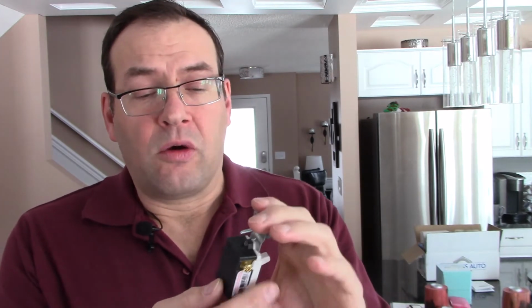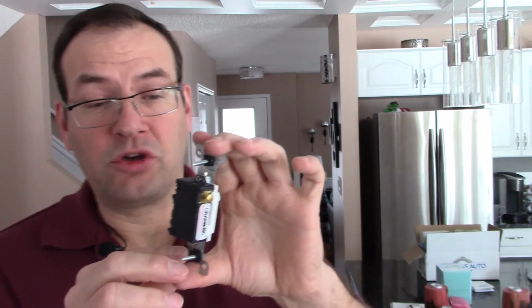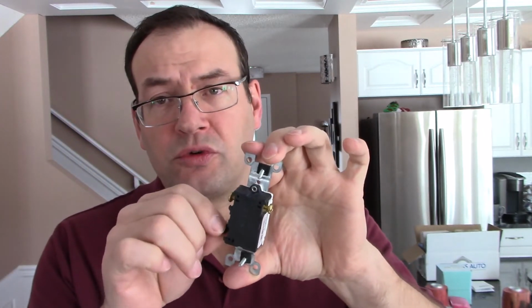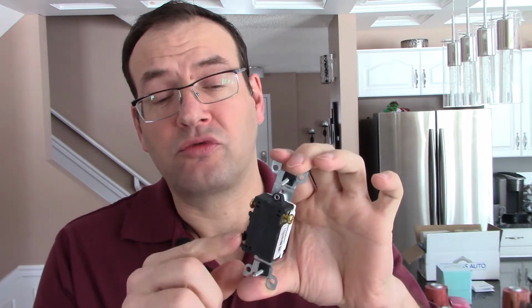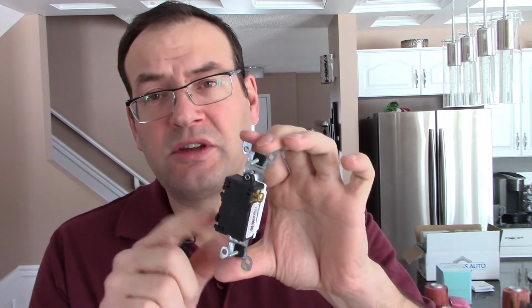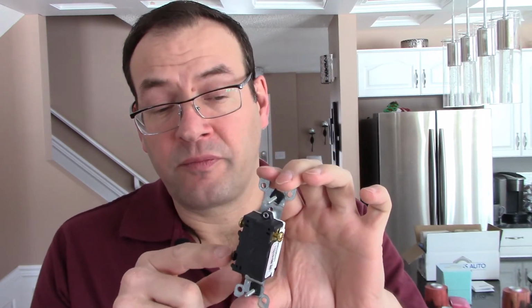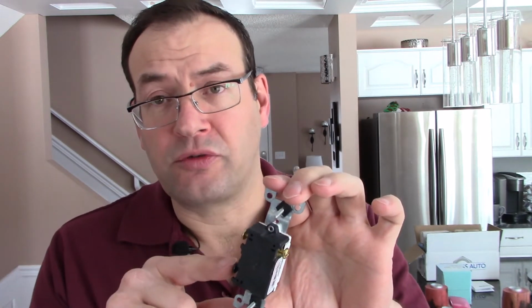So when you take the old switch out of the wall, if you're replacing it, we have to make sure that whatever wire was on this brown screw, when you took it out, it's usually identified as a black screw or a brown screw, or sometimes it's a silver screw and the other ones are brass. But whichever identified screw that this is, that wire must go back on the common screw, or your 3-way circuit won't work anymore.